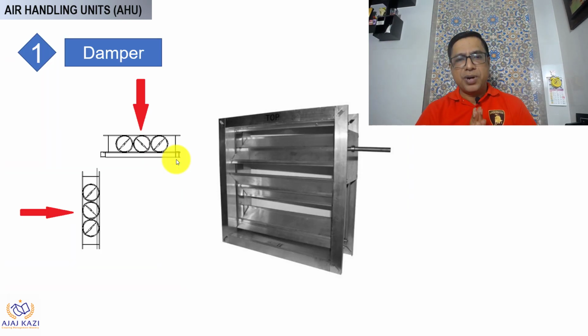Let us now look at the components of air handling units. First important is the damper. As I said, this is where the return air comes in, and it has to have a damper. The function of a damper, the picture is in front of you, is to throttle the air quantity, to adjust the air quantity. It has a damper at the return air and also at the fresh air. Both get mixed in the mixing chamber, but to have the proper quantity of air, the adjustment has to be done by this damper. This is how the damper looks.